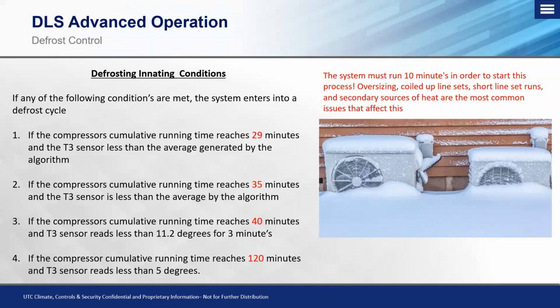So once we meet that 10-minute minimum runtime, we have certain conditions that will start initiating a defrost. So the first one's going to be if that compressor's runtime reaches 29 minutes. So again, that takes into that 10-minute minimum runtime, but a total cumulative running time of 29 minutes. And the T3, which is our outdoor coil temperature sensor, reads less than the average generated by the algorithm. That's going to be the first scenario that we're looking at.